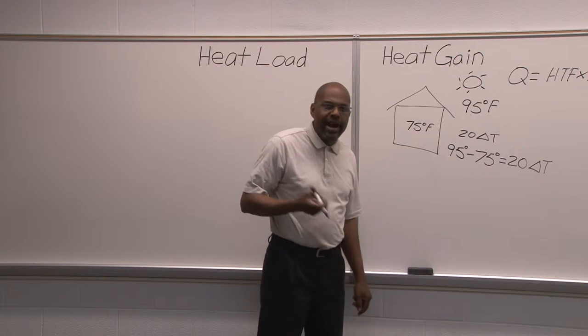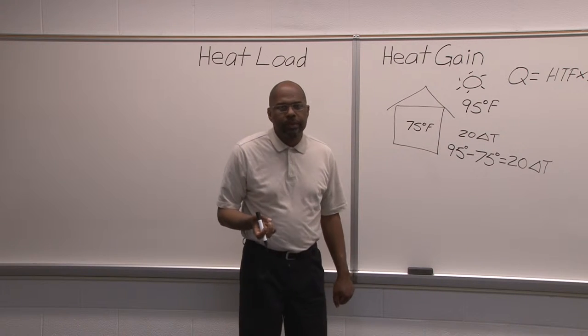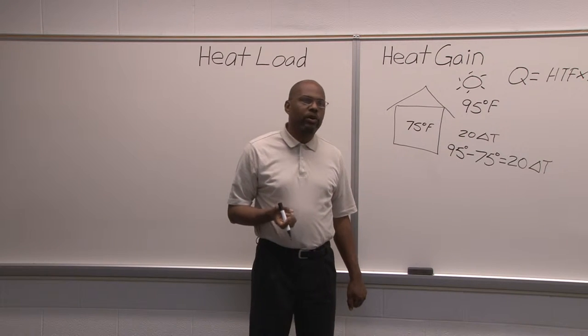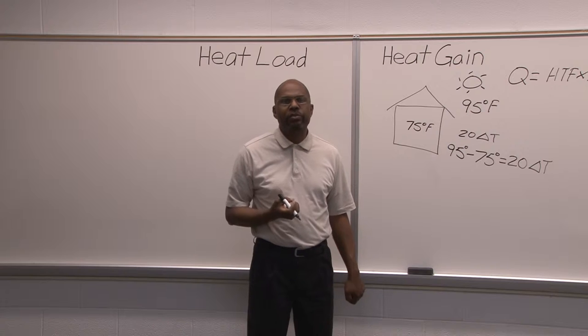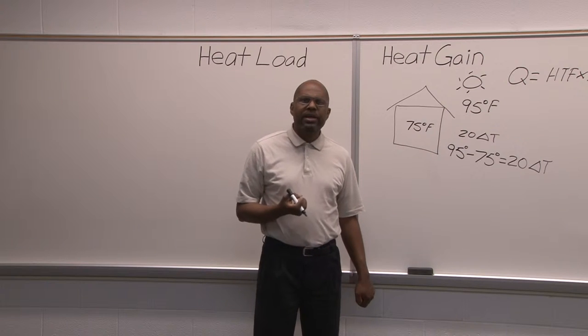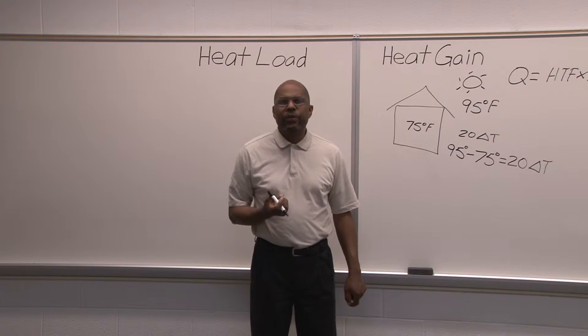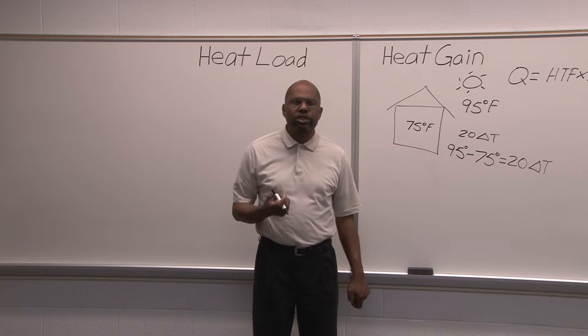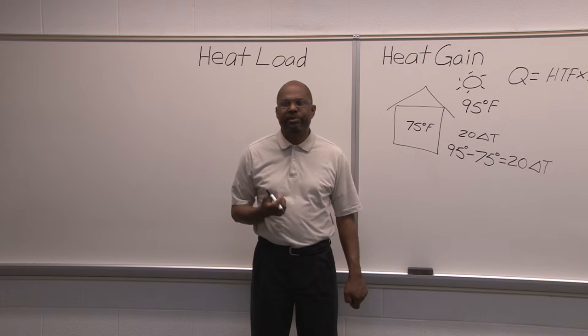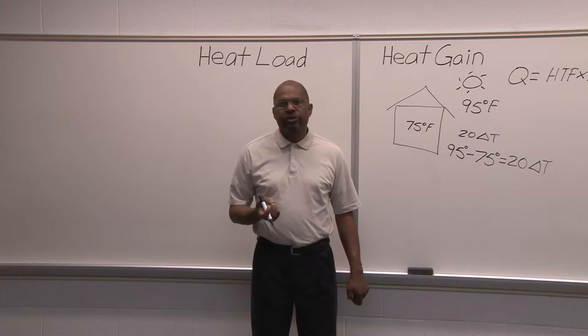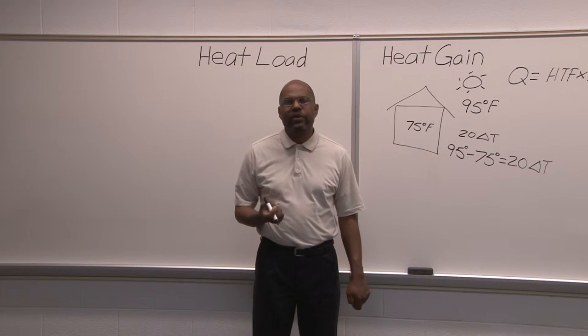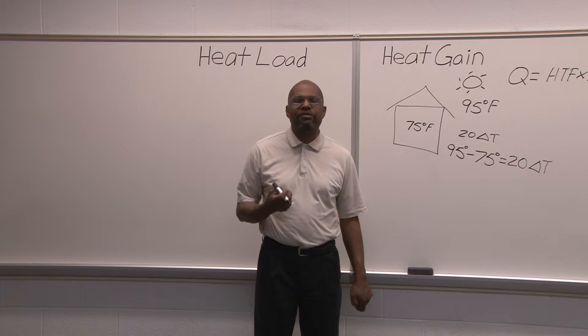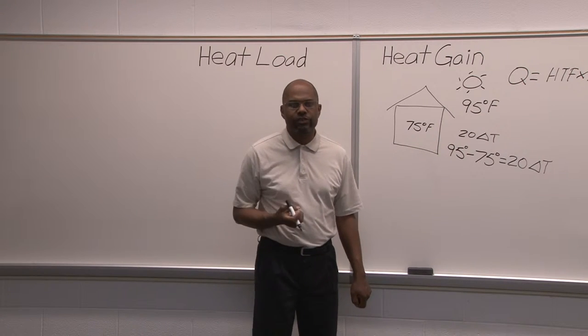So if it's 20 degrees, that delta T is set. If it's higher than that, of course, that delta T will be higher and the amount of heat transfer will be higher. But here's the thing: we cannot change the structure of the house every time the temperature changes. So thereby, we must design for the worst case scenarios, or the most average temperature we know it would reach in the different seasons.